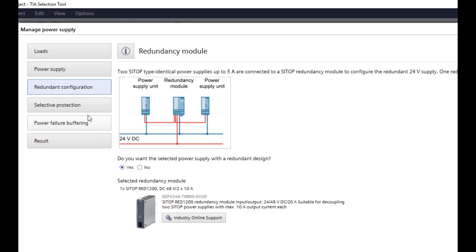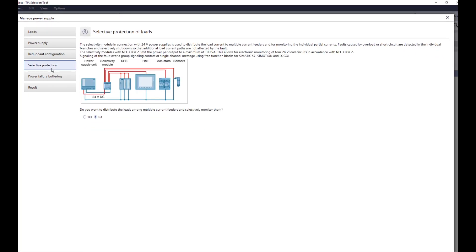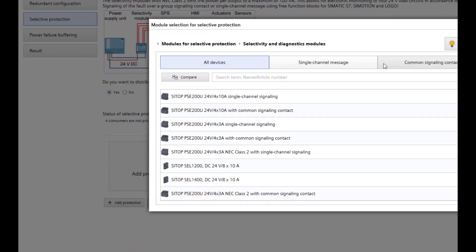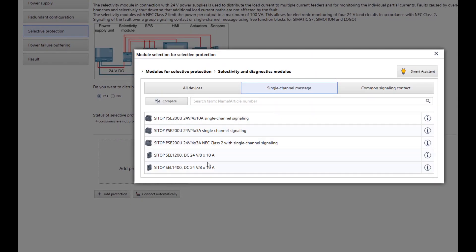Now an important and decisive device can be selected when it comes to the availability of the 24V: the selectivity module, which in the event of a short circuit or overload only switches off the affected branch so that the remaining outputs can continue to be supplied. For this purpose, the Selective Protection button has to be clicked on the left side of the wizard. After answering the question of whether the branches should be split up and monitored, the module can be added. The required and suitable device can be specified in the following selection window.